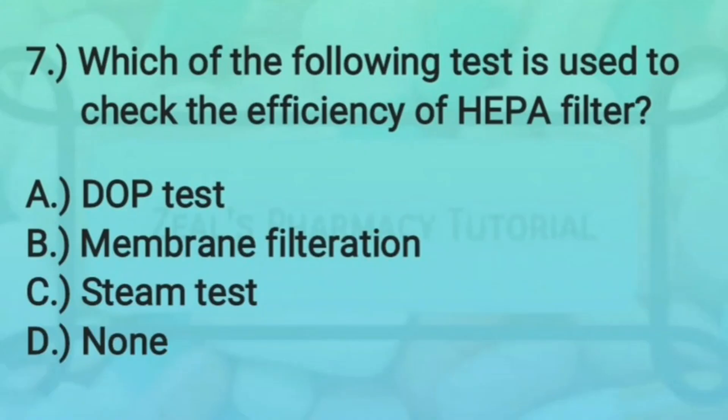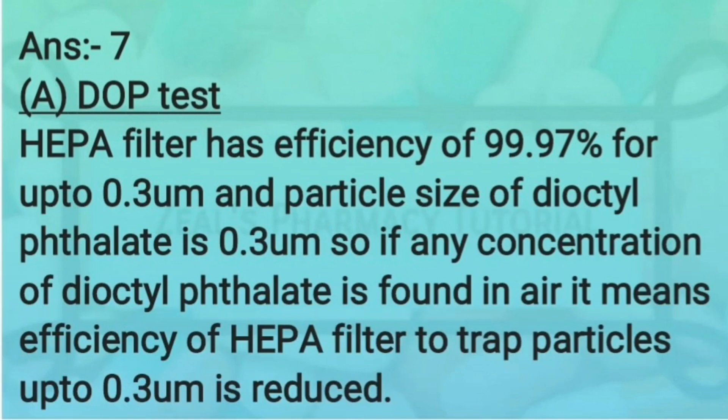Question seven: which of the following tests is used to check the efficiency of a HEPA filter — DOP test, membrane filtration, steam test, or none? The correct answer is the DOP test. The HEPA filter has an efficiency of 99.97% for particles up to 0.3 micrometers. The particle size of di-octyl phthalate (DOP) is 0.3 micrometers.